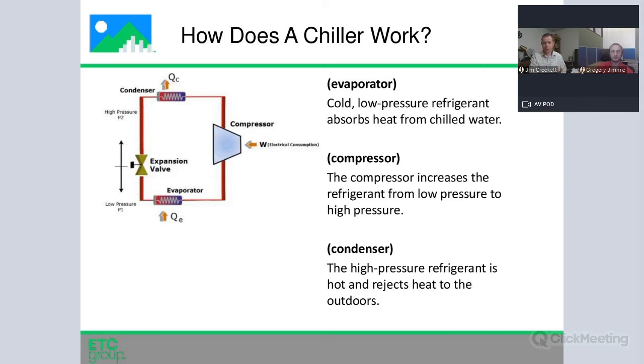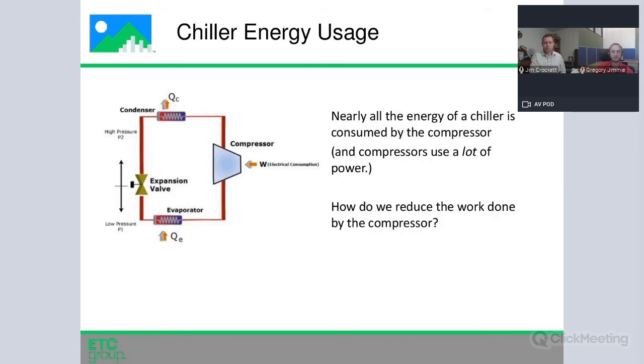We'll come back to all of this in just a minute. We're still doing an overview, but the reason we're going to focus on the compressor is because nearly all of the energy used by a chiller is used by the compressor, and they use a lot of power. When you walk into a 200,000 square foot office building and go into the chiller plant and look at the chiller compressor, probably 25 or 30%, depending on weather, of the overall power being used by the building is used by that single piece of equipment. So if we can find a way to reduce the compressor's energy usage by 10%, we're reducing the overall building by 2 or 3%. We're dropping our power bill by 2 or 3%.